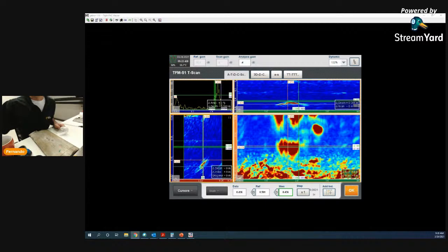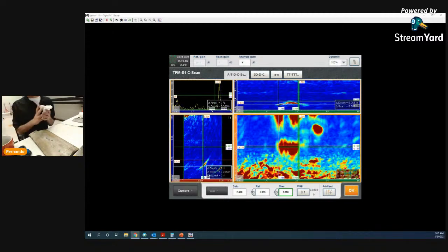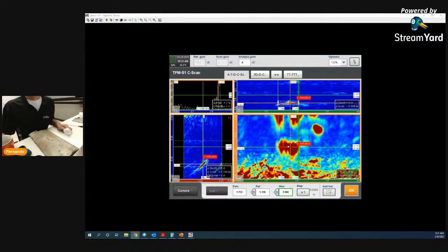So here's another thing we can do. Say I want to measure the distance. I'm going to go distance, and I can put a cursor there. We'll go up. See, my indication starts there. I can move this cursor depending on where the indication stops. So I can go here, measure, and then lock it in. Then it tells me the distance over here on the bottom right. The distance is going to be 0.669. So you can add the indication to the report.